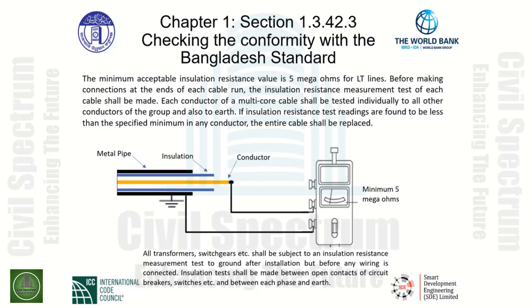As seen in the graphic below, we have a megger that is actually inducing a voltage through the conductor and tied on to a metal pipe. This test is testing for any leakage coming through the insulation from the conductor.